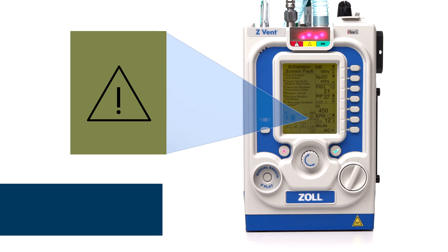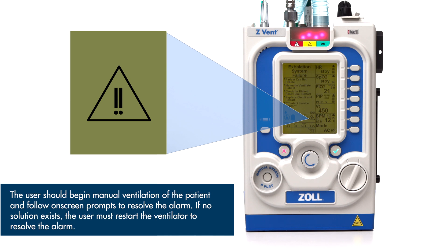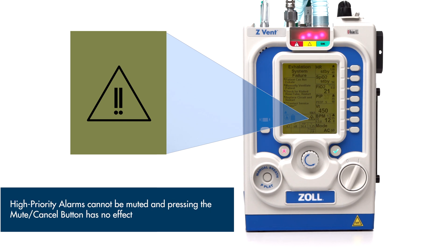If the alarm trigger is still present after 30 seconds, the audible alarm recurs until muted. During a high priority alarm, mechanical ventilation is no longer possible. This alarm requires immediate user intervention. The user should begin manual ventilation of the patient and follow on-screen prompts to resolve the alarm. If no solution exists, the user must restart the ventilator. The LED array will rapidly flash red accompanied by a fast audible tone. High priority alarms cannot be muted, and pressing the Mute-Cancel button has no effect.